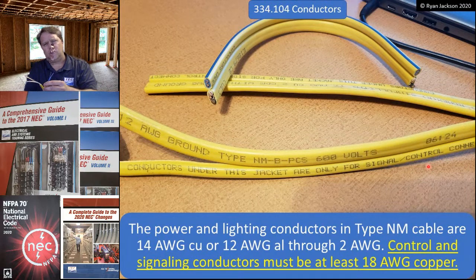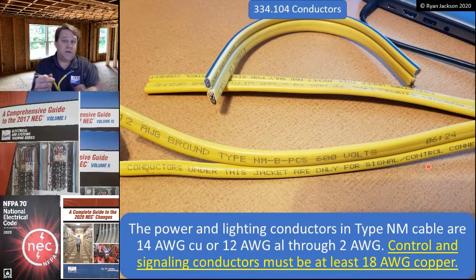Not sure how often you would use that with NM cable. That's kind of a commercial thing, at least for right now, but there's certainly other lighting control options where this could be a real nice option. So they do manufacture it, complies with the separation requirements in 725.136 because this is all NM cable. Do you need separation between NM cable and like a thermostat cable? No, the cables could be touching each other, and that's essentially what we have here. Even though this is more robust than a thermostat cable, it actually is non-metallic sheathed cable. So kind of a cool little solution.